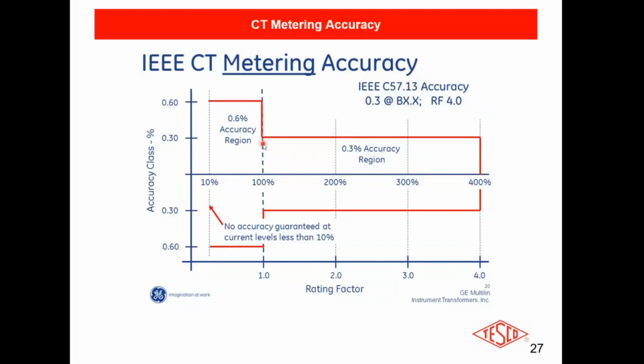Once you go down to the rated number, 400 in this case, because it's a 400 to 5, your accuracy doesn't jump as a step. It actually does more like this, but for idealized purposes, what you'll typically see is a step function. It actually doubles to 0.6%. If you read the faceplate of that transformer, do you know where you will see that information? The answer is nowhere. You will never see it. It doesn't show up. You're just supposed to know it. You're supposed to know that below 100%, its accuracy goes in half, meaning it goes from 0.3 to 0.6%.